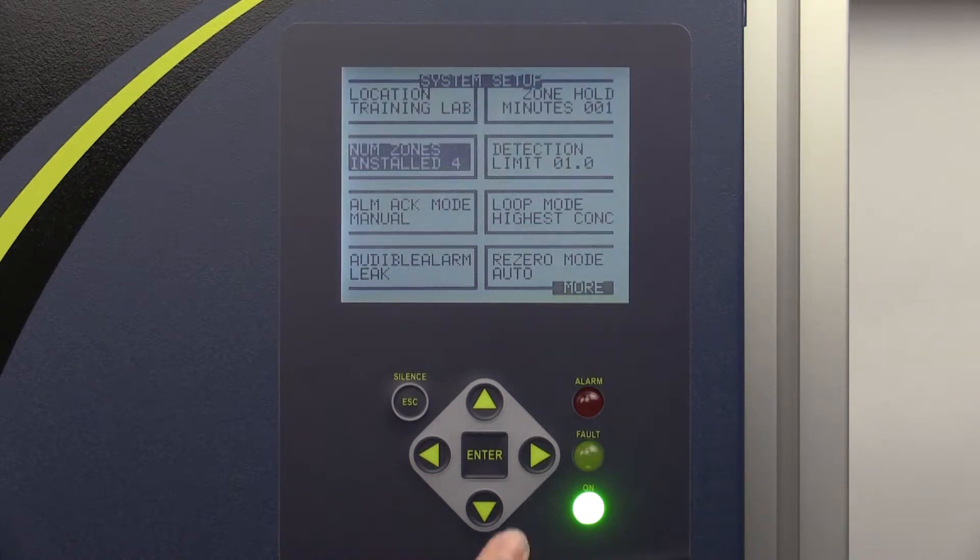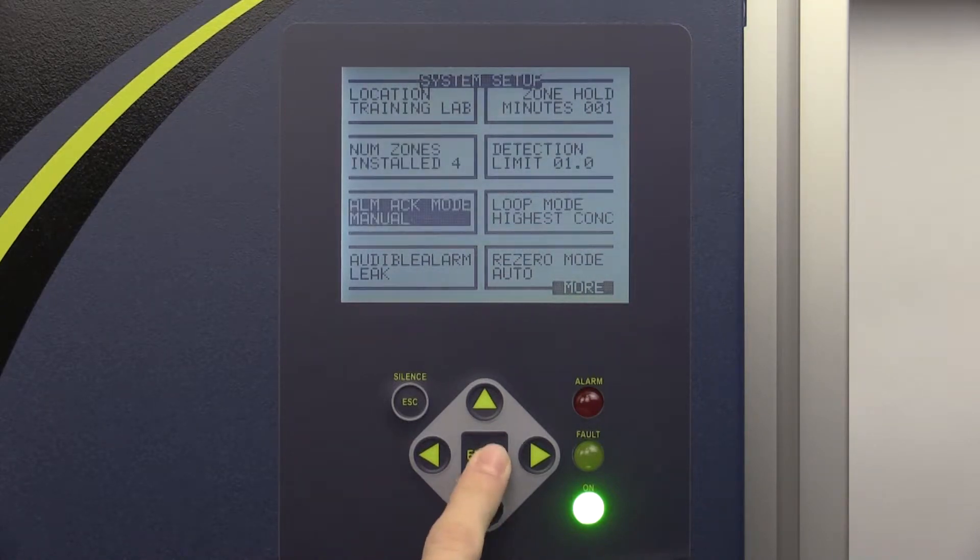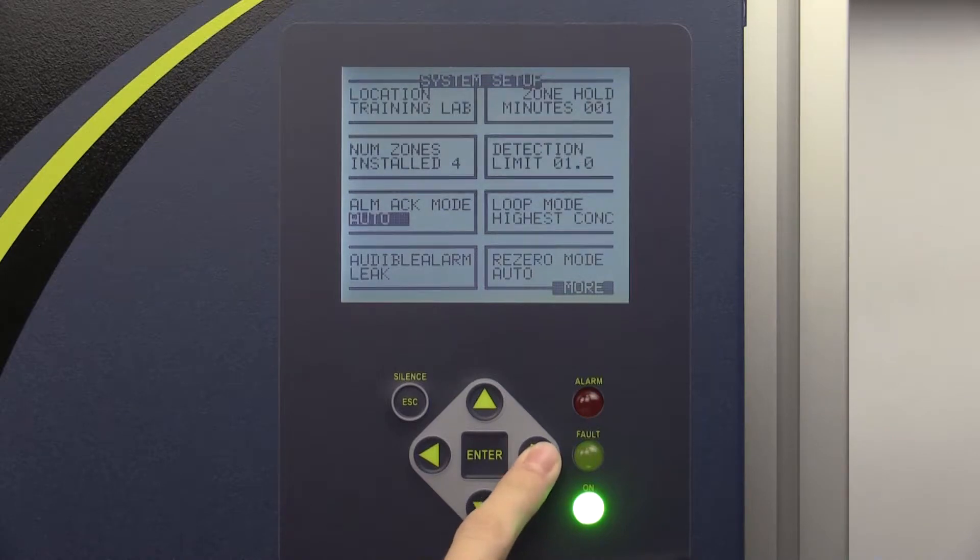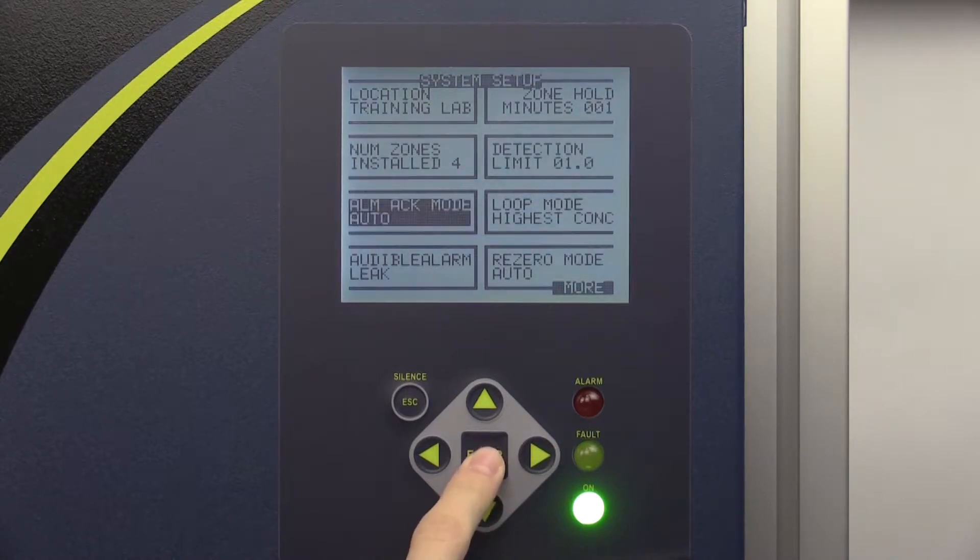Alarm acknowledgement mode has two options. When the auto option is selected, the monitor will automatically acknowledge any triggered alarm. Once an alarm is acknowledged, it will shut off once the PPM reading has fallen back to a safe level at the zone.